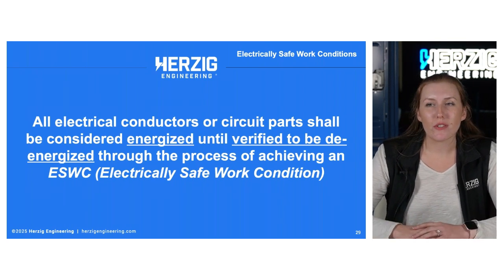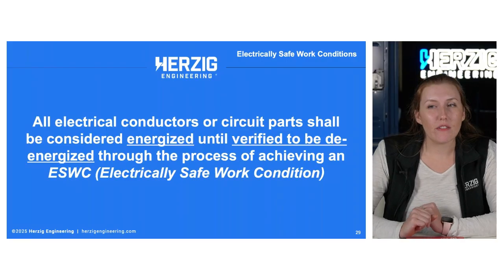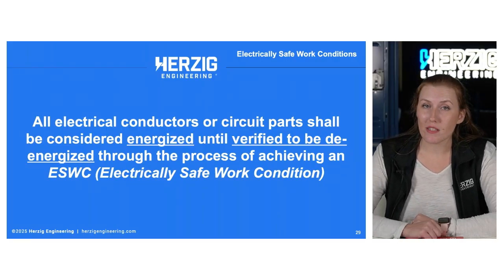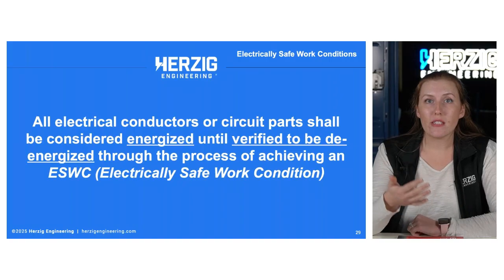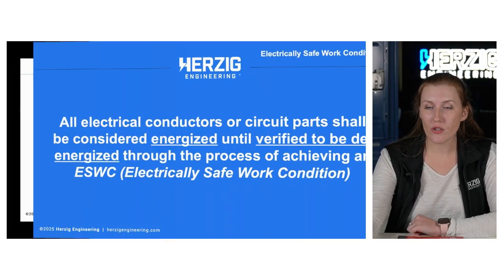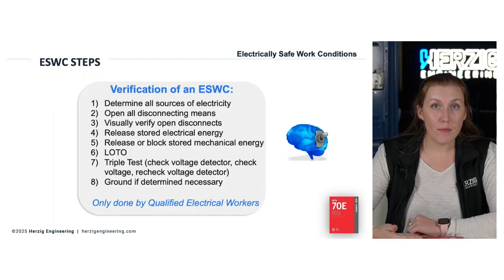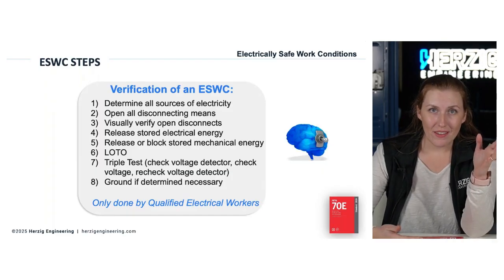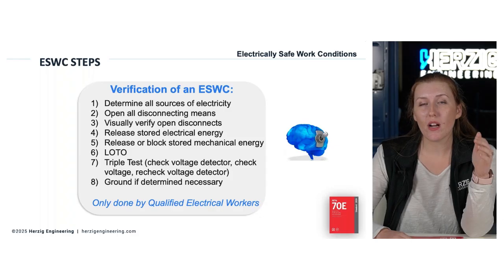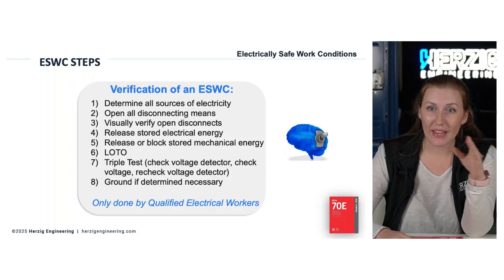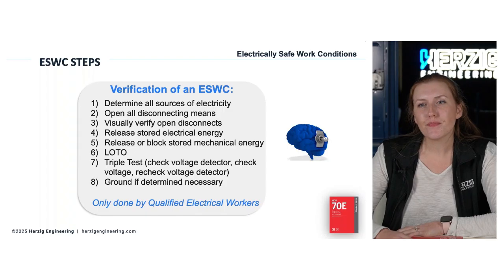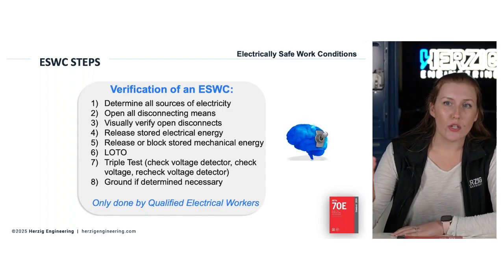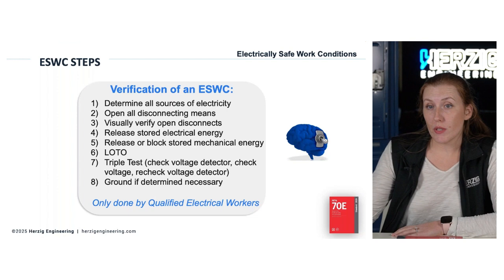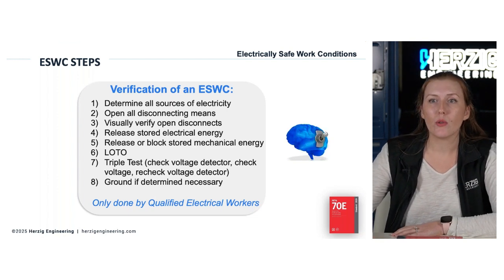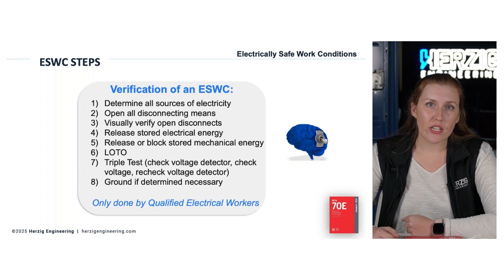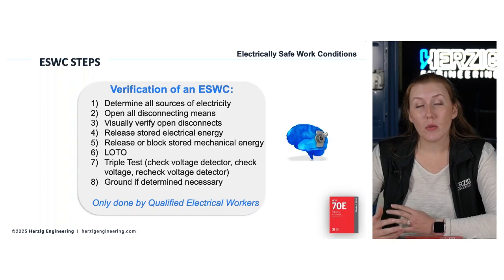All electrical conductors or circuit parts shall be considered energized until verified to be de-energized through the process of achieving what we call an electrically safe work condition, which, if you break it down, is really 8 steps with an assumed step that you're going to be putting on PPE and boundaries and doing your job safety plan before you start this process. So it's going to be qualified persons determining the sources and opening the disconnects, doing visual verification as possible, releasing stored electrical energy, releasing or blocking stored mechanical energy, and applying lockout tagout.